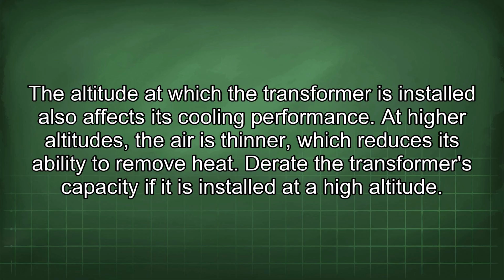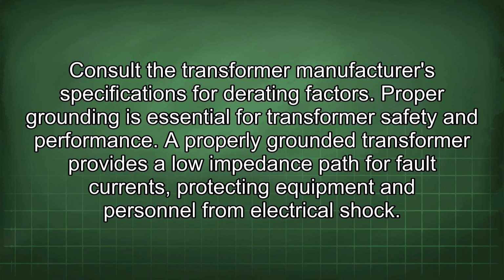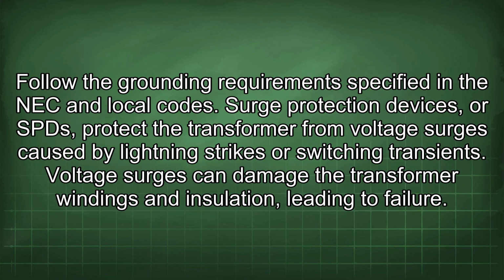At higher altitudes, the air is thinner, which reduces its ability to remove heat. Derate the transformer's capacity if it is installed at a high altitude. Consult the transformer manufacturer's specifications for derating factors. Proper grounding is essential for transformer safety and performance. A properly grounded transformer provides a low impedance path for fault currents, protecting equipment and personnel from electrical shock. Follow the grounding requirements specified in the NEC and local codes.